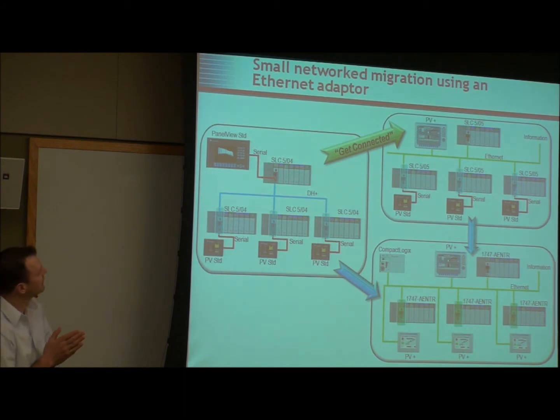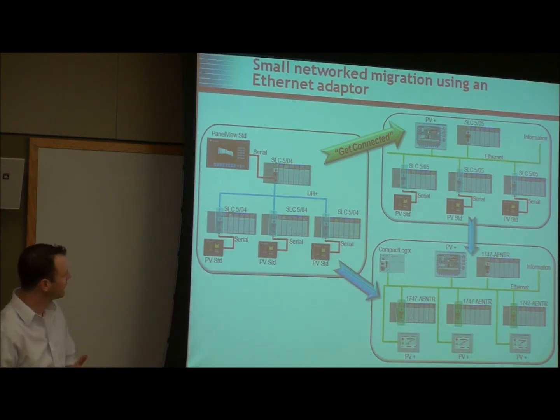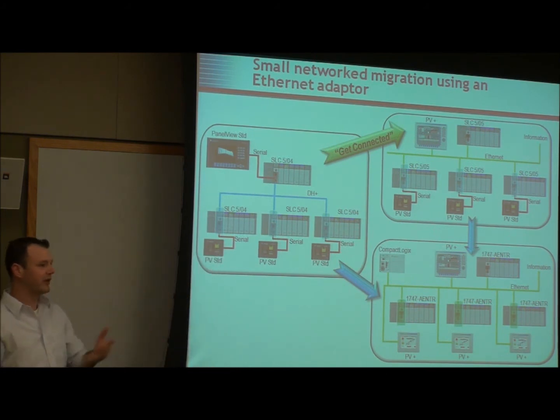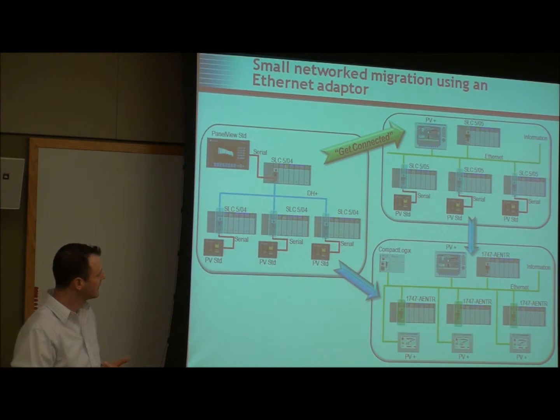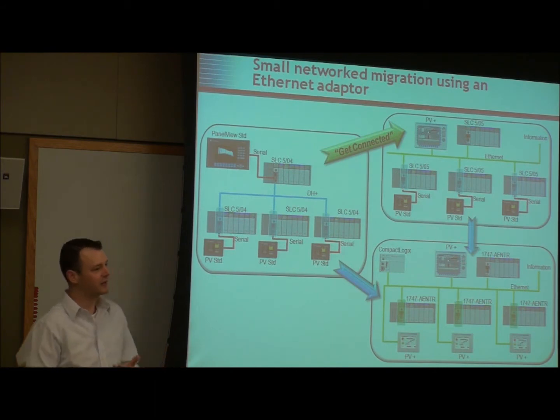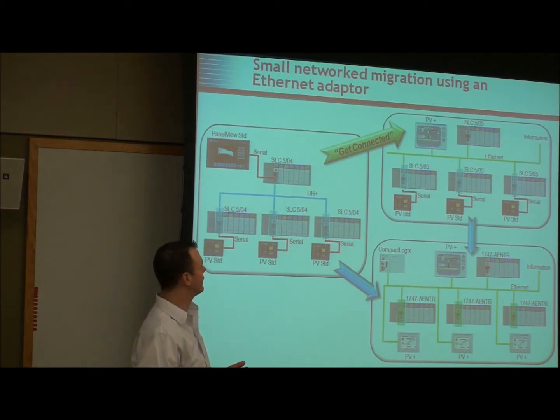There are a couple of different paths you can take. You can do it all at once — take all your SLC I/O, put in your AENTRs, and build an Ethernet network off of that. We talked about risk mitigation, though — doing everything at once is not necessarily your best option. Another way to mitigate risk is to go from the SLC 504 to the 505; you're not really changing a program that way.